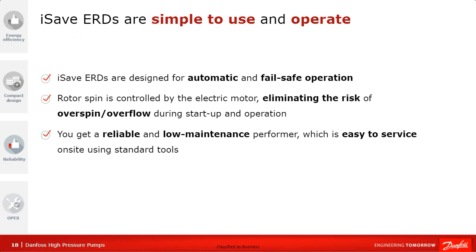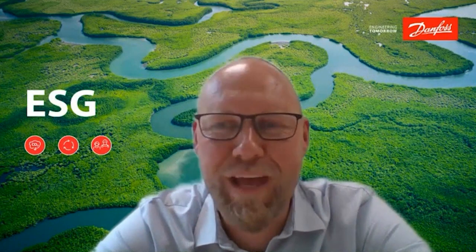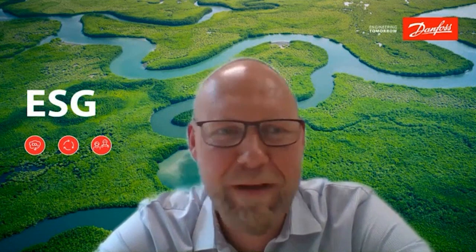The iSave is designed for automatic and fail-safe operation. The drive monitors the iSave and ensures everything is in order — the rotor spin is controlled by the drive, which eliminates any risk of over-spinning or overflowing during commissioning, startups, and operation. This means you get a very reliable, low-maintenance ERD. It also makes troubleshooting easy since you know exactly how the ERD operates, what flow you're getting, what flow you should be getting, and what the speed of the device is. That covers the iSave and axial piston pumps — we are ready for questions.